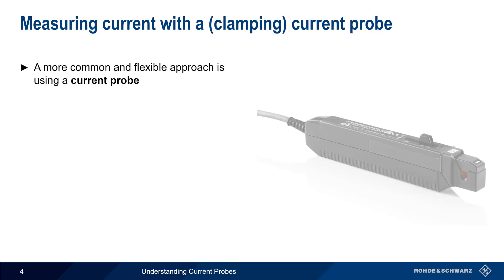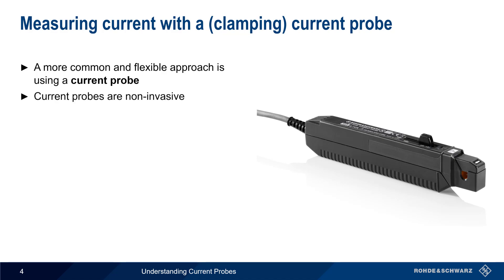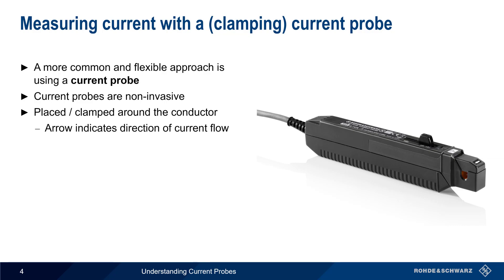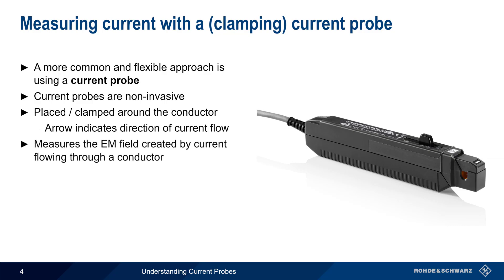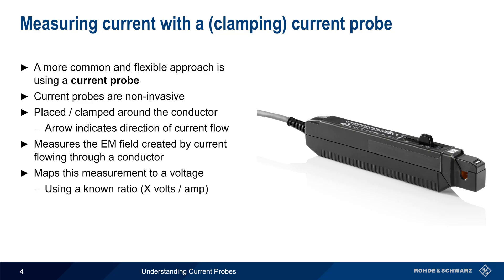A more common, and in many ways more flexible approach, is using a special current probe. Current probes are a non-invasive way of measuring current — there is no need to break the circuit. These probes are placed or clamped around the current-carrying conductor, with an arrow marker indicating the direction of current flow. Current probes work by measuring the electromagnetic field created by a current flowing through a conductor, and then mapping this to a voltage using a known ratio of volts per amp.